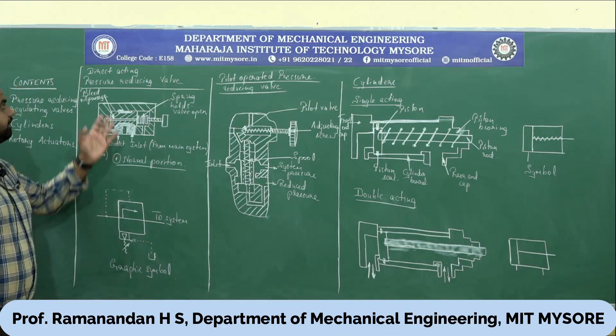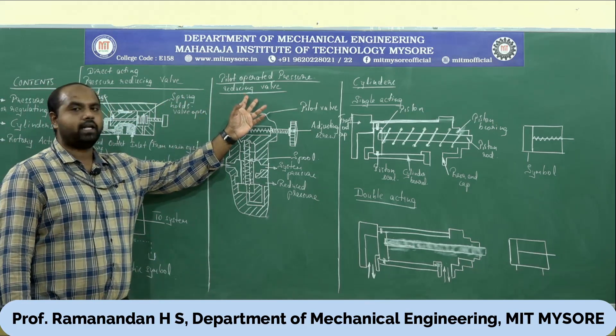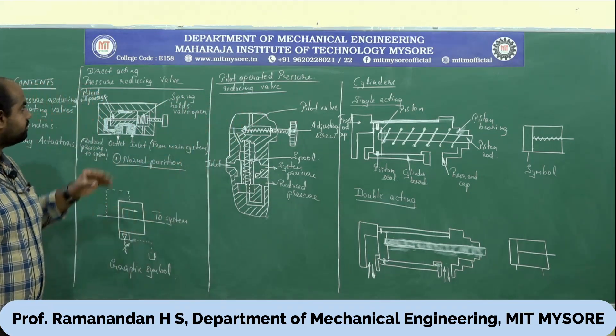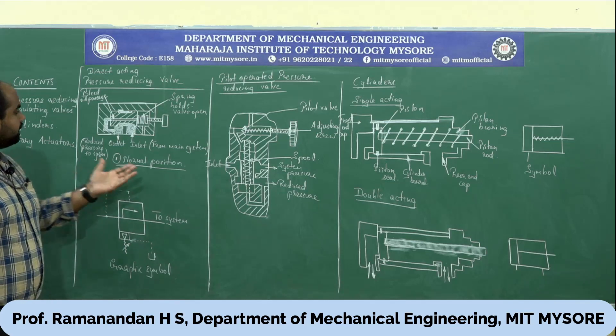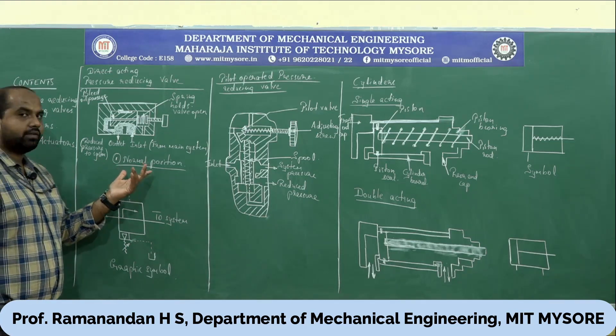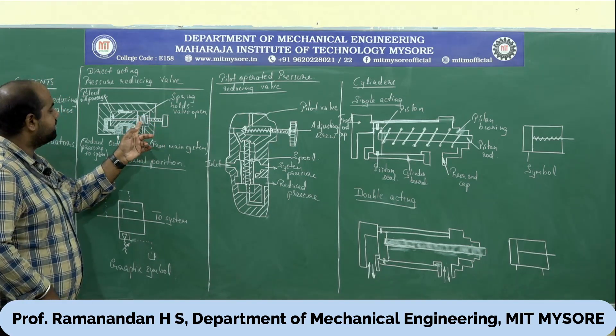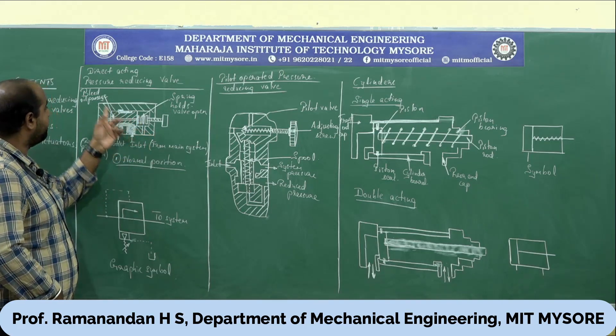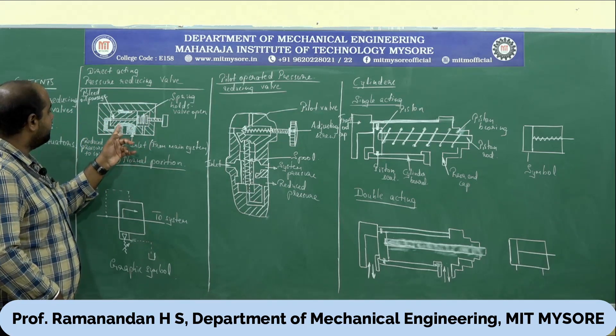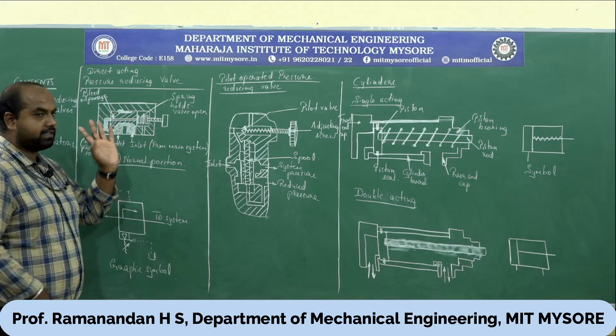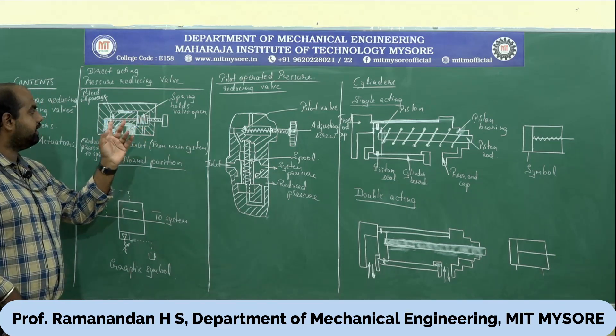We classify pressure reducing valves into two types: direct acting pressure reducing valve and pilot operated pressure reducing valve. Looking at the direct acting pressure reducing valve, this is the normal initial position of the valve. You can see here there is an adjusting screw assisted by a spring, and this is the bleed oil passage. This is the external casing, and there is a connection between the outlet and the bleed oil passage.